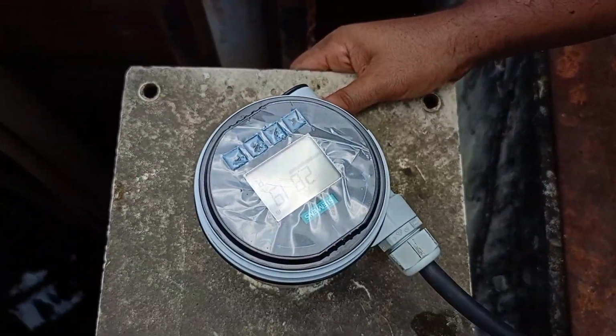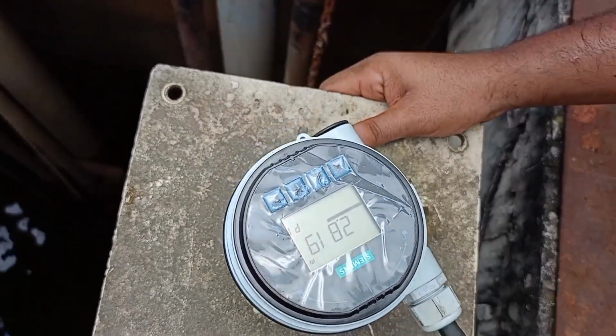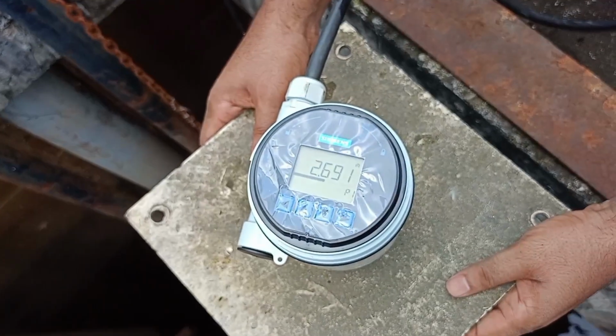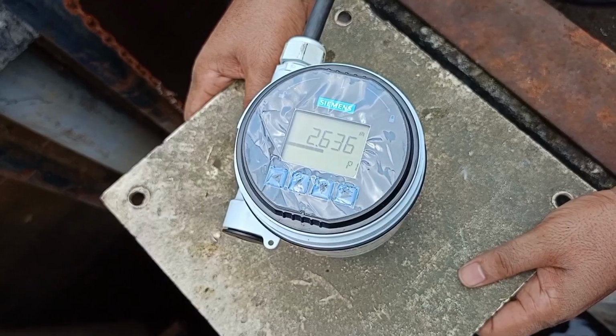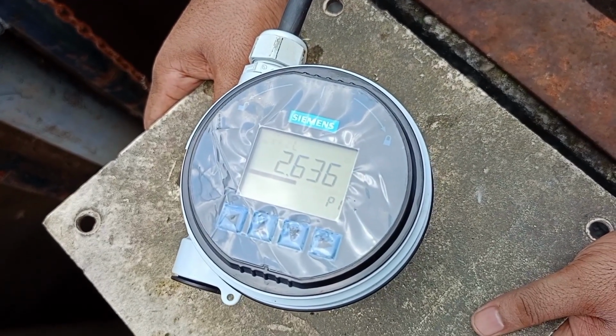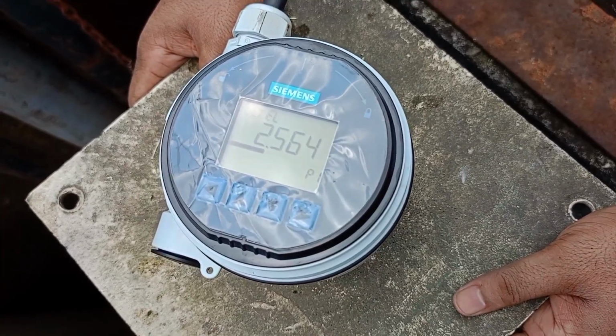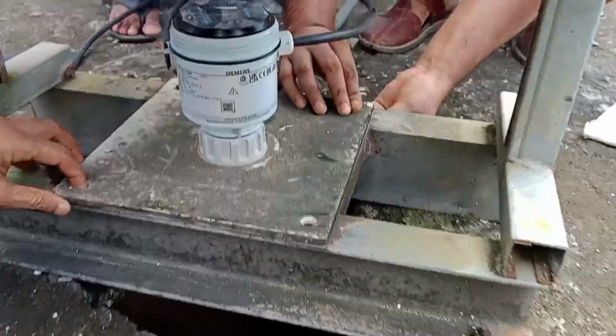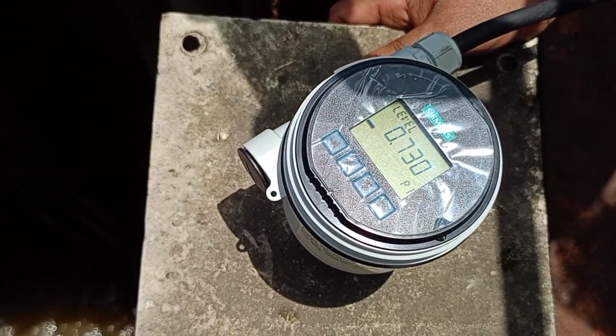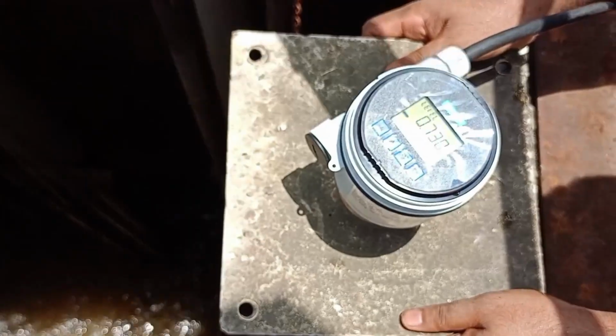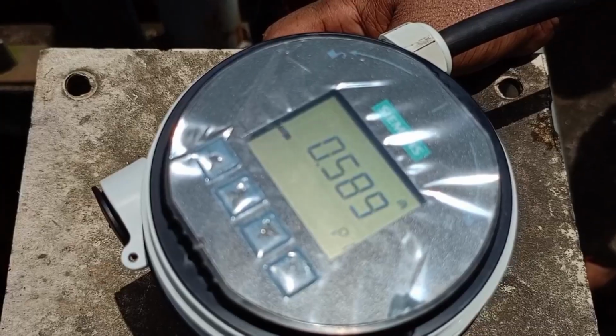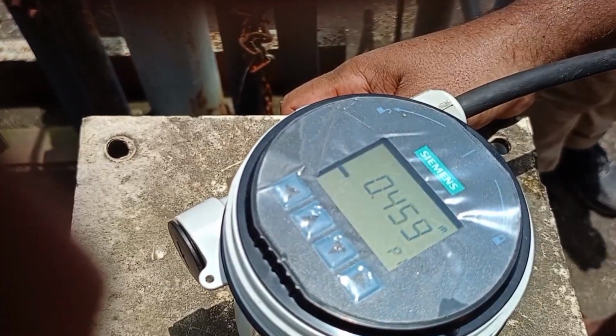After completing commissioning, setup and field calibration, now we will install the transmitter at our field directly on the vessel, and then we will check the actual level. At first we dismantle the old one that was not working properly, and instead of this we connect the new one. After connecting and data setup and also calibration, temporarily we check whether the level value is showing or not. That means with the increase of level, it is working or not, its value is increasing or not. We followed this, and then we install this transmitter on its base, and we verified that the transmitter is working properly.